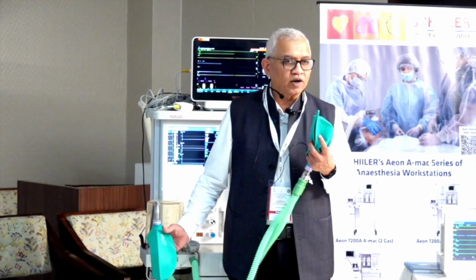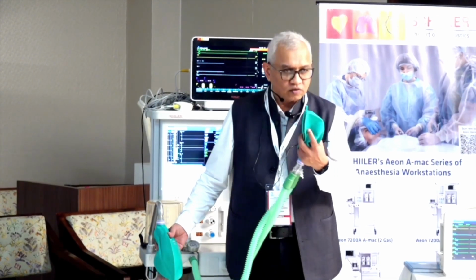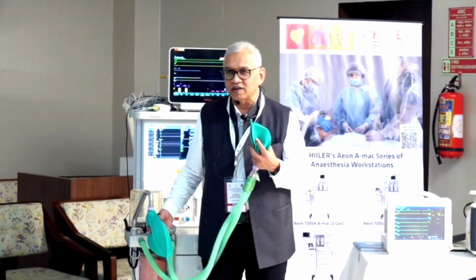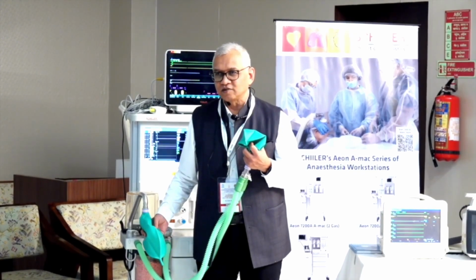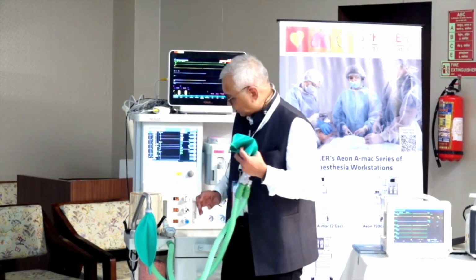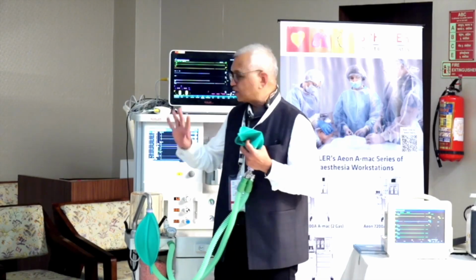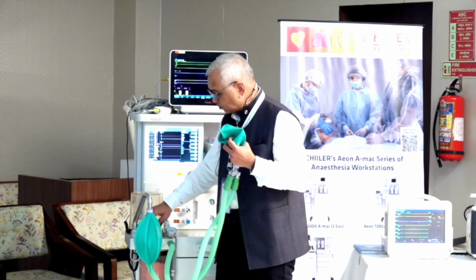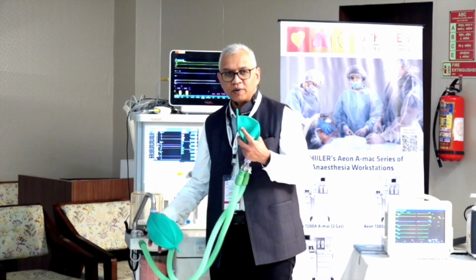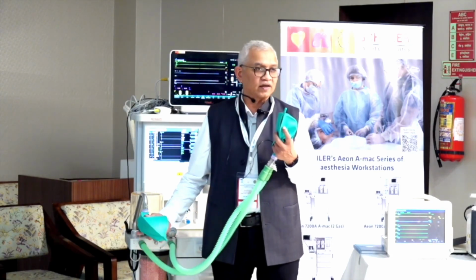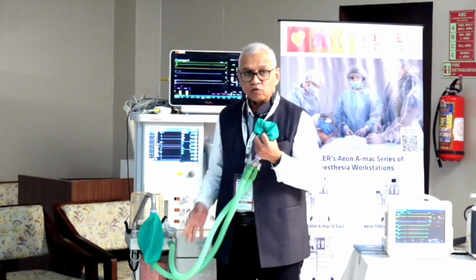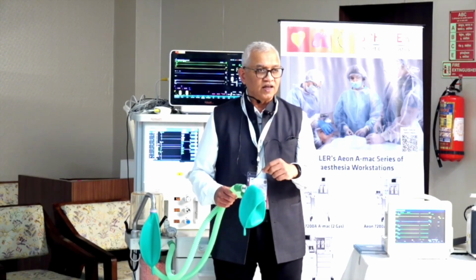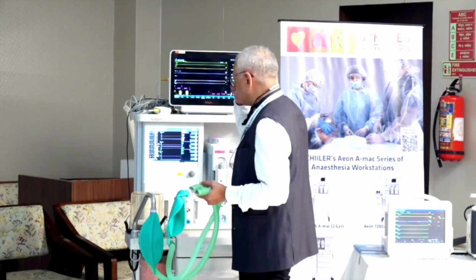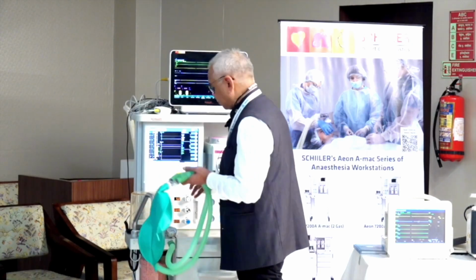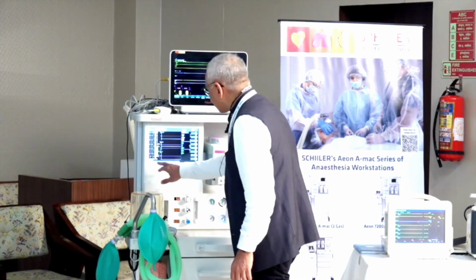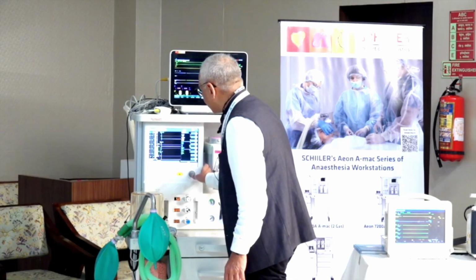It is very, very important. Many times you might have seen, those who are senior and who have worked for a very long time, that it gets stuck. So it is very, very important that before starting, even after doing a pre-test, this is something which you can always do. Close the APL valve and try to squeeze both the bags. So this is called the two bag test. Now to check whether this machine has a leak or not, we have to switch it to the ventilator mode. So we have made the flow 5 liter. Okay. And then I'll switch to IPPV.